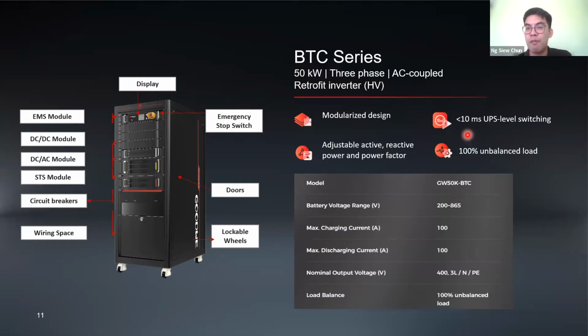Besides having this fabulous feature of less than 10 milliseconds UPS level switching, our PCS also supports adjustable active power, reactive power output, as well as power factor correction functions. At the same time, it also supports 100% unbalanced load. So especially for our customers in C&I applications, it's very common that they will have unbalanced load over the 3 phases. And there's no worries about that. Our PCS will totally support it. And this is extremely suitable for the telco application in Malaysia.